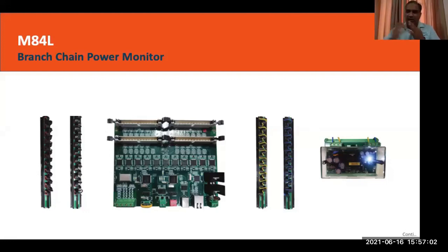Wherever I have limitation of space, in my PDU or IT company, but I still want to monitor all the energies, powers and currents at one place, because I cannot physically put meters on all the dBs, this is the product for that. It's a plug and play CT strip. One CT strip has 21 inputs, so up to 21 single phase meters, or 7 three-phase meters, can be monitored with this one module, and you can put up to a maximum of 4 strips in one branch chain monitor.